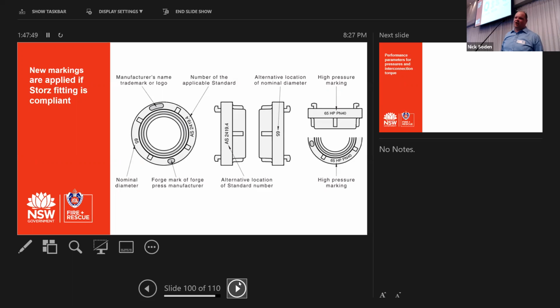Potentially, they may manufacture a whole batch of new Storz and they might get some new casting dies made up, in which case you might actually have AS 2419 Part 4 on the actual top where you normally see NEN 3374. And on the right-hand side, you'll see there's a new high pressure variation. So one of the interesting things is in fire brigade boosters, you have a PN35 booster, but you don't actually have a high pressure rated Storz coupling at the moment. There are stainless steel PN40 Storz, but you can also get aluminium alloy rated to 4,000 kPa. And they need to be marked with HP.